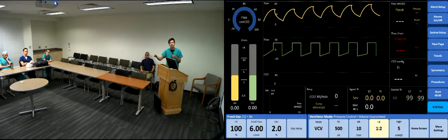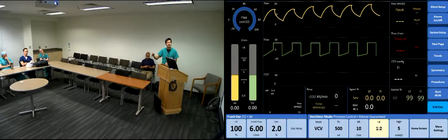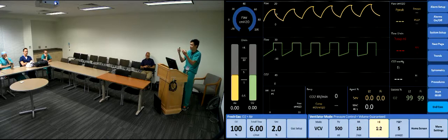So that's what it looks like on the flow side. But on the PEEP side, the pressure side, it'll make a little more sense because you're auto-peeping, right? You're building PEEP with each breath. And so you can see the amount of PEEP, or positive end expiratory pressure, is building up with each breath. You see that? So it just starts stacking up. And that can result in high airway pressures eventually and problems with that. So giving them a longer I:E time will give them more time to get that air out. Okay?